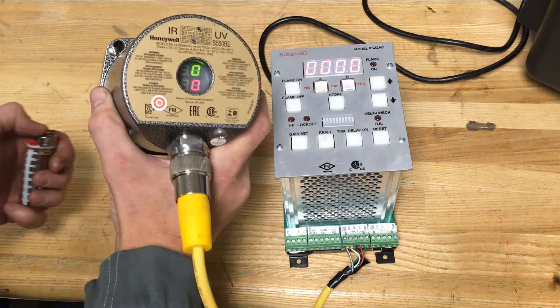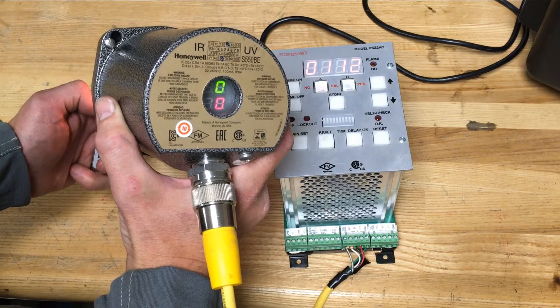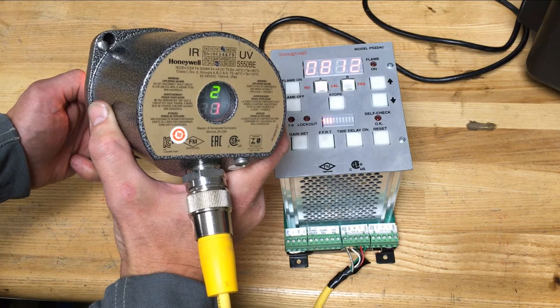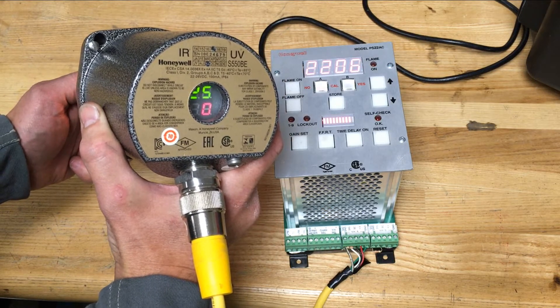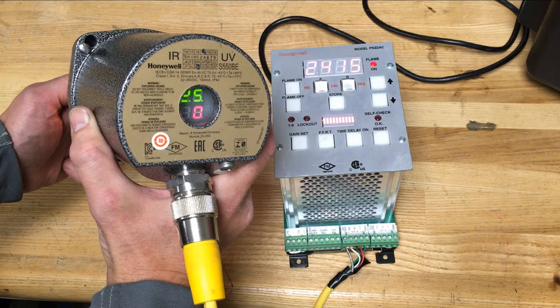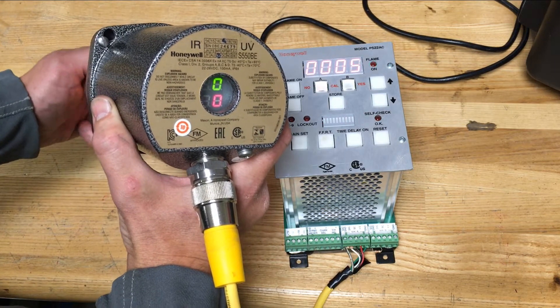The UV cell can be tested with a standard lighter and will be represented by the green LED on the viewing head. If the flame is dancing around it will also trigger the IR cell.